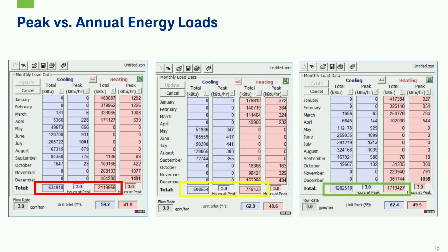Then if you move to the middle graphic, we have better peaks. In the cooling in July, we have a peak of 441 kBTUs per hour. In heating, we have 434 kBTUs per hour in December. I'm thinking, okay, great, this is balanced. Look at these peak loads, they're almost equal. You couldn't ask for anything better. But then when you look at your annual loads, we have 500,000 kBTUs of cooling over the year, and then we have about 750,000 kBTUs of heating over the year. So there's still about 1.5 times greater, and so there's still a pretty significant heating imbalance.